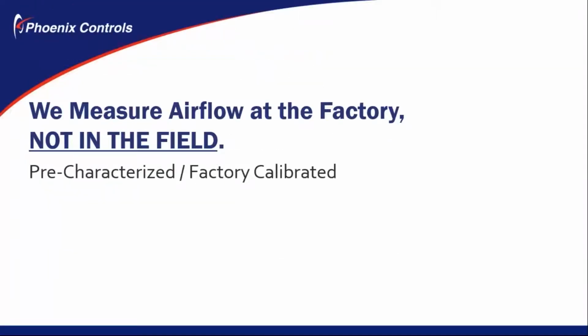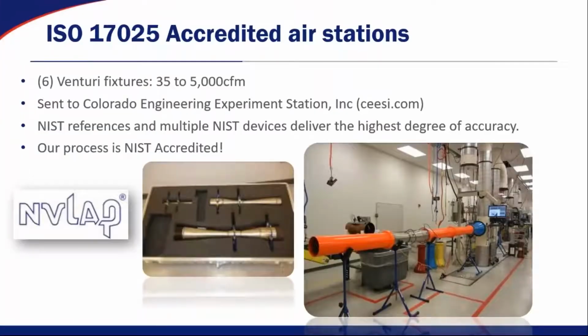Now, I mentioned that we don't measure airflow in the field, and that's true. However, when the valves are characterized at the factory, we do measure airflow in the factory. So Phoenix has 6 air stations inside of our manufacturing facility, and these are ISO 17025 accredited air stations. So our entire calibration process of our valves is actually third-party certified. When we calibrate the air stations quarterly, we actually use NIST traceable devices, and that picture you see on the right with the orange ductwork is actually showing you how we calibrate the air stations.